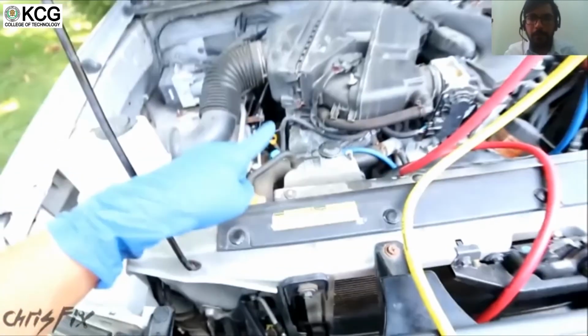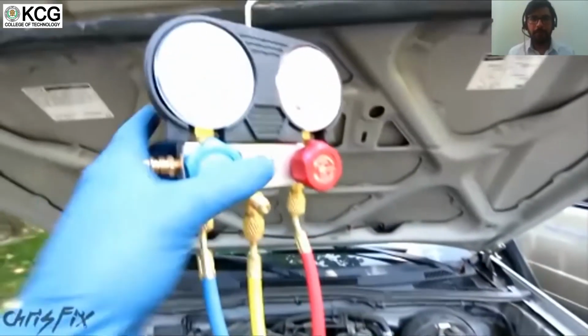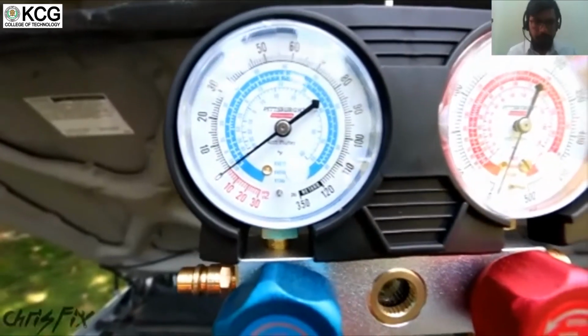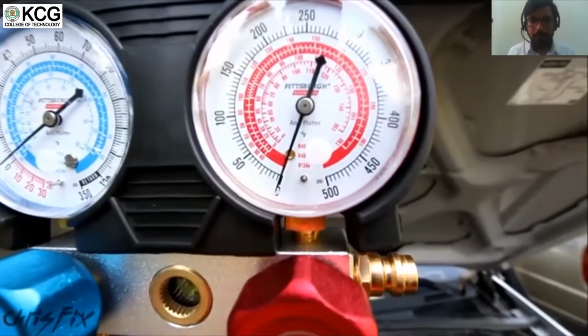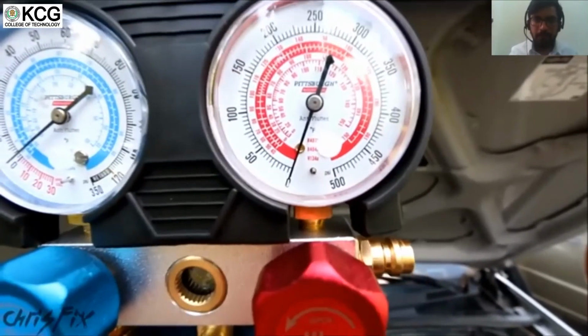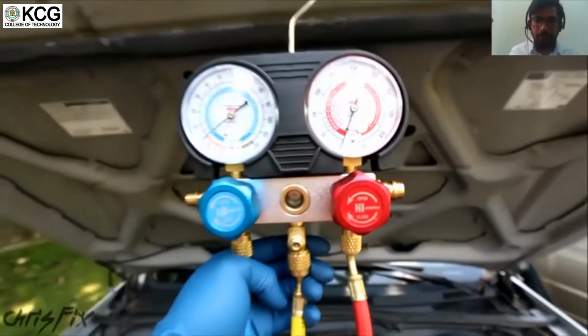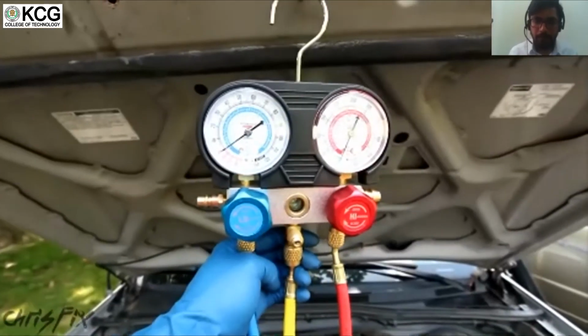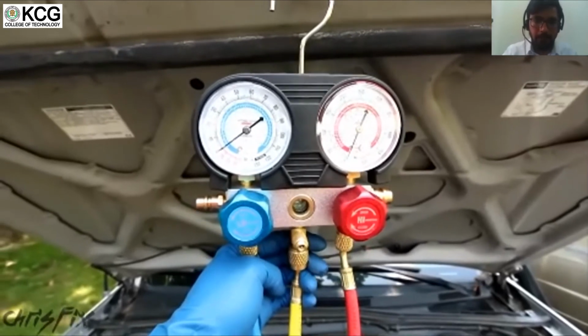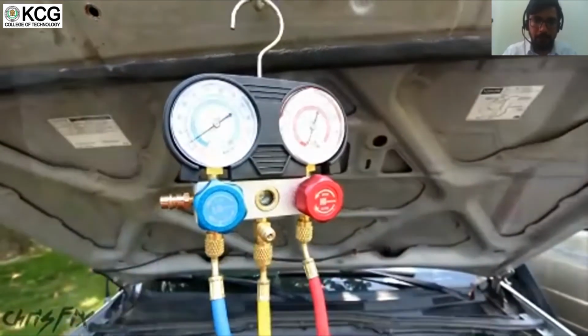With the high and low pressure side opened up, you can see here at the low side it's at 0 psi, which is exactly what we want. And you look here at the high side, it's at 0 psi, which is exactly what we want. So there's no pressure in the system, obviously. We know that because we replaced the compressor. Now we can start pulling a vacuum. The last line we have to connect is this yellow line, which is going to go to our vacuum pump. And I'm just going to move this down because my vacuum pump's going to be on the ground.